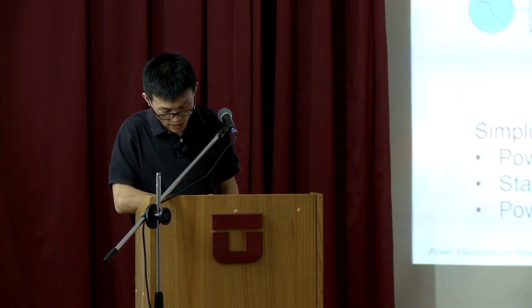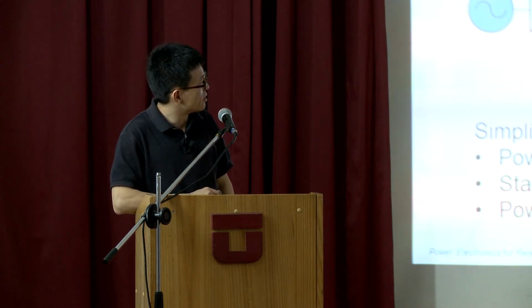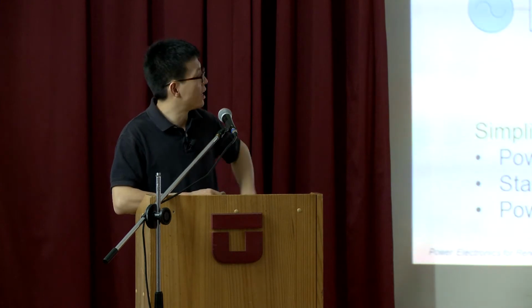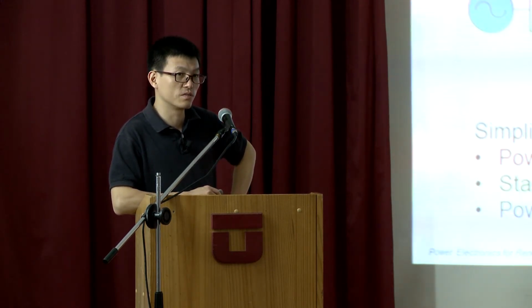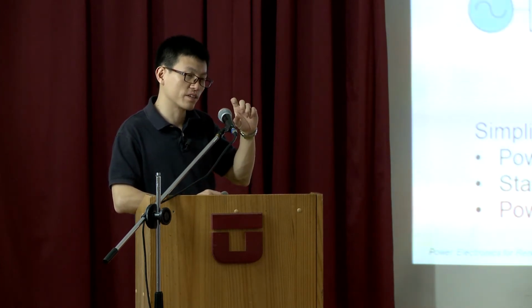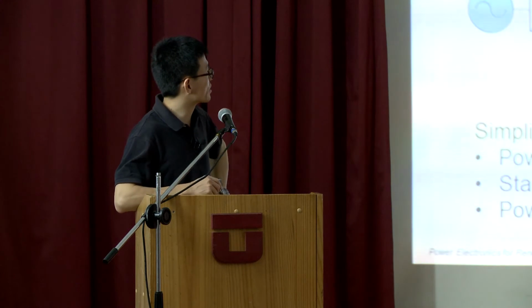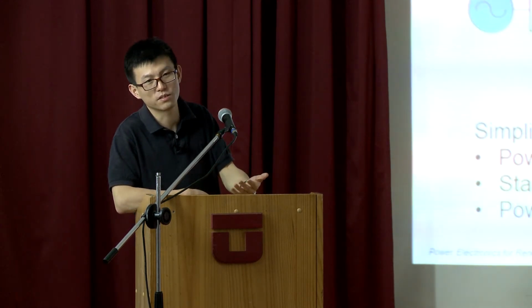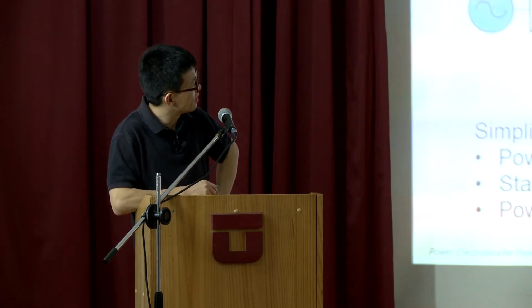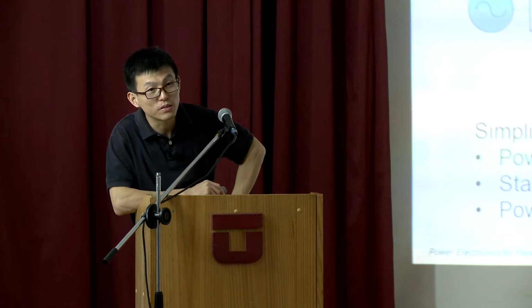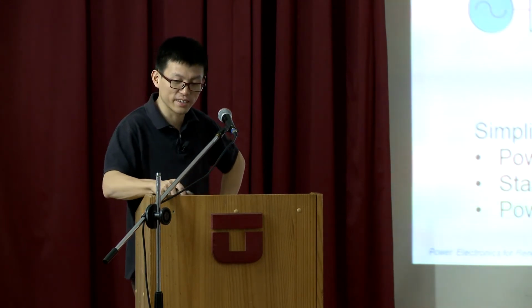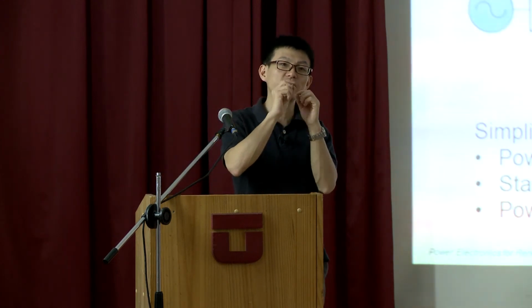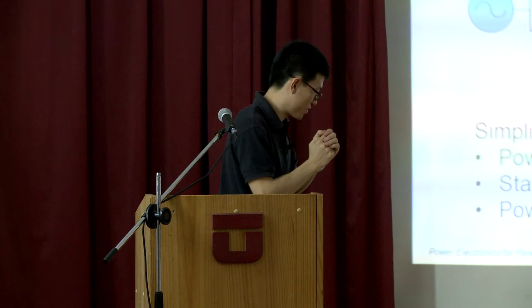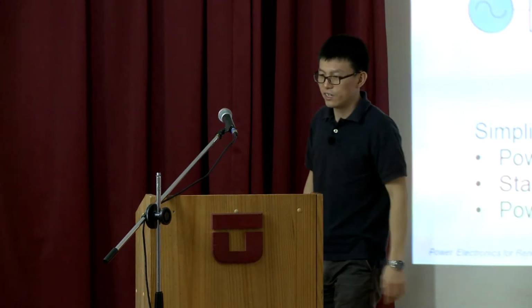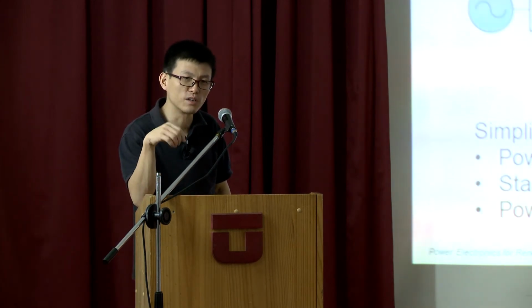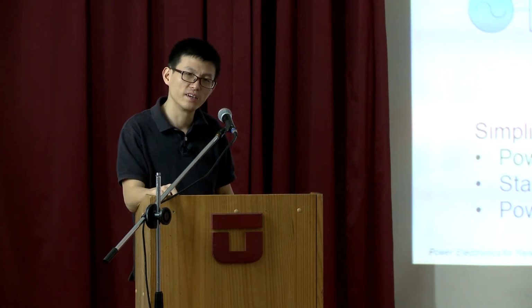For some other projects, we try to push to 100 kilohertz. But the problem is the dV over dt. You switch very fast, and what the machine sees is the line-to-line voltage, the DC voltage on this side. So it switches very fast, the dt very short. If the DC bus voltage stays constant, say 540 or 1080, you get a very high dV over dt value, which affects the machine's insulation layer, the copper, the winding. You have an insulation layer, and if you see a very high dV over dt, the life cycle of this insulation layer is much shorter.